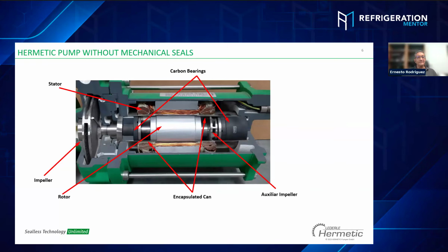Is that correct? Yes, correct. Basically, oil is the problem because when you have a different density of the fluids, for example, oil, and the oil in low temps is very thick in ammonia. In CO2, we don't have this problem, basically. Okay. It runs freely. The only problem we have is a flash gas. We can't prevent the flash gas. The problem is it can't make the lubrication correctly and the cooling correctly.